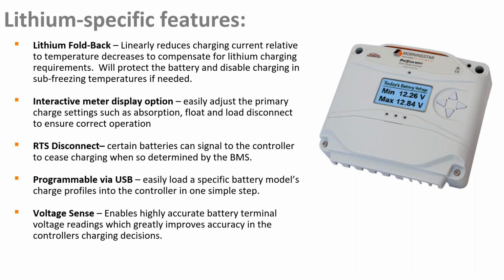What we allow is for the user to program a foldback derate. In our custom settings, you can specify a high temperature and a low temperature threshold, specifying a range over which the controller's output will linearly derate as temperatures get colder. It's nice because it still allows you to harvest as much power as possible and continue charging the battery, since temperatures might pop back up - you don't want to cut off the current completely, so it operates on a linear spectrum.